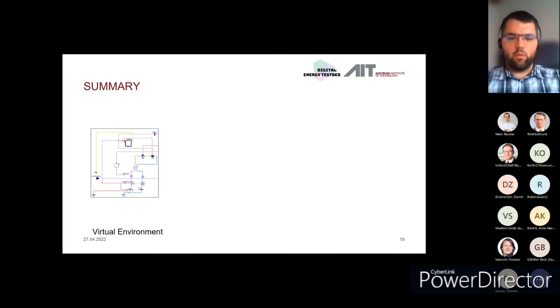So first of all, on the virtual side, our building model, and this is then connected via LabLink and this B&R automation system, on the one hand with the real environment, the secondary side of our test bench, and with the district heating substation. So the model gives us the set point of the flow temperature, which is then the set point for our two-way valve of the substation. It gives us the return temperature set point, which is then the set point for our three-way valve. It gives us the mass flow, which is controlled within the building model to reach the specific inner room temperature. And this is the set point for our two-way valve on the secondary side. And we get back the actual flow temperature, which is then the input for the building model in the end.